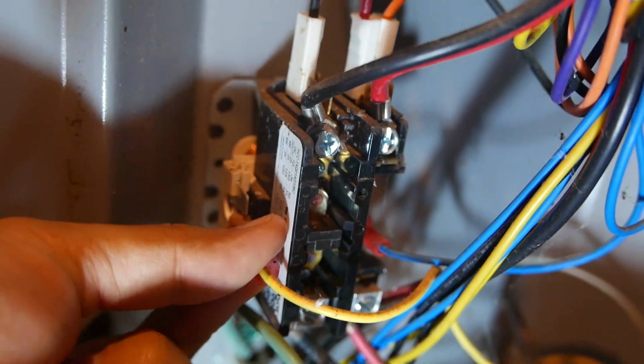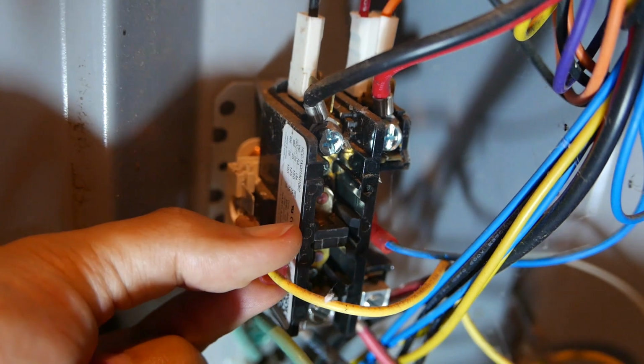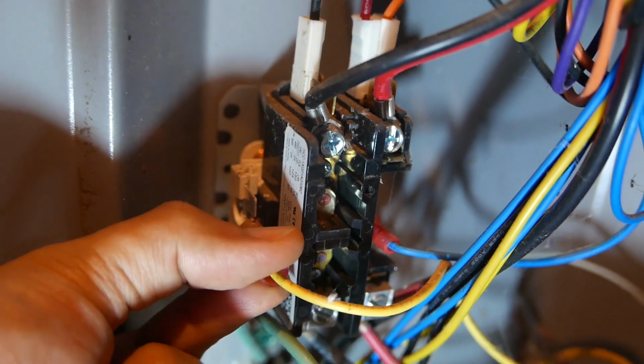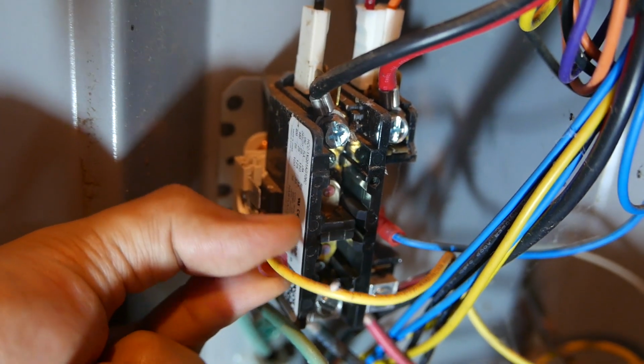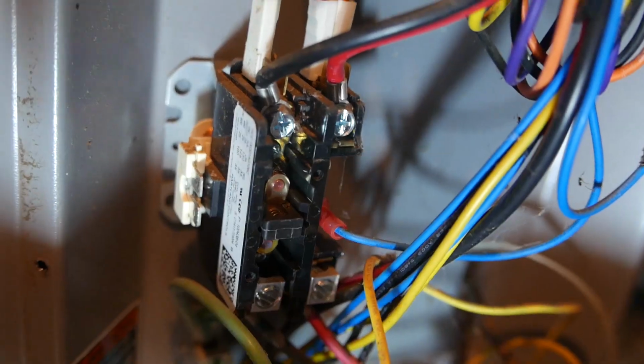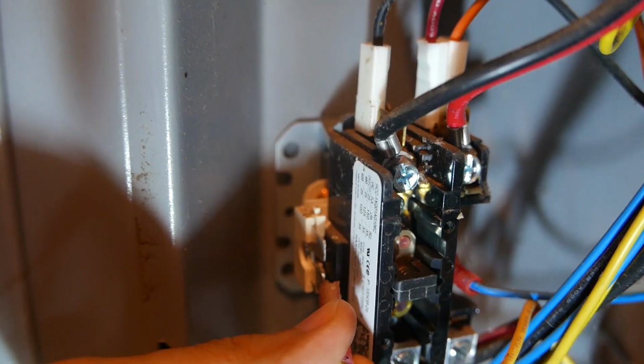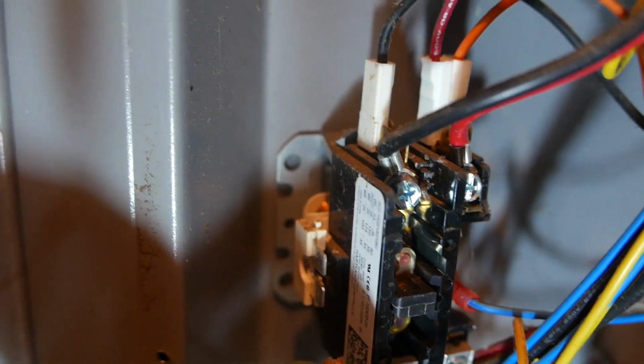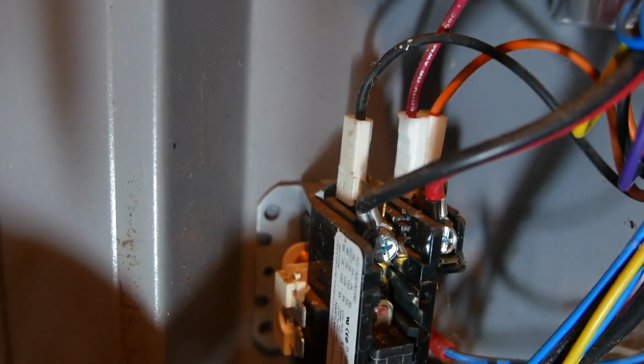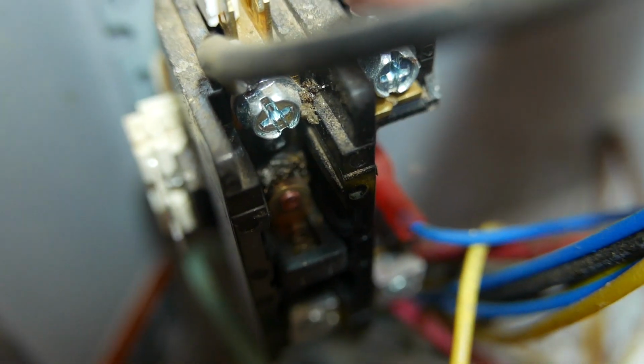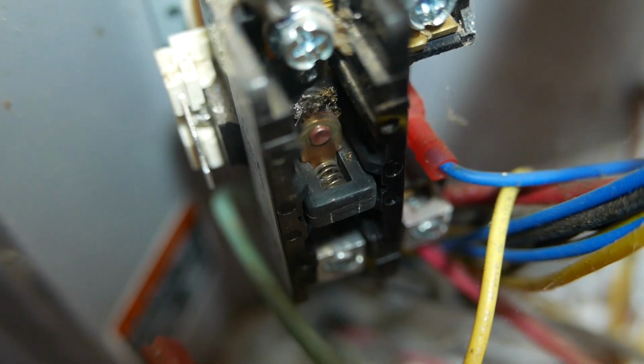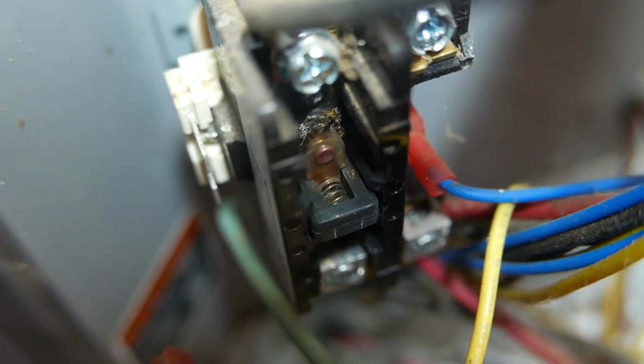There's still 24 volts trying to shut this relay down. Let's remove the 24 volts and see what happens. So it was closed, but the voltage wasn't passing through. Right there, you see how dirty and bad that contact is? That's the reason why it's not working.